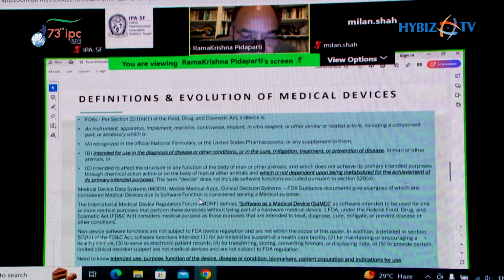Again, software that serves as electronic patient records is not a medical device, which is what we call the EMR and EHR, electronic medical record or electronic health record. And for transferring, storing, converting formats, if you have some X-ray or MRI and you move it from one location to another, it is not a medical device. If, on the other hand, something can read that MRI and come to a diagnosis, then that will be a medical device. If it is software written as an image analyzer, as we talked about earlier, that will be a device, but this is not going to be a device.